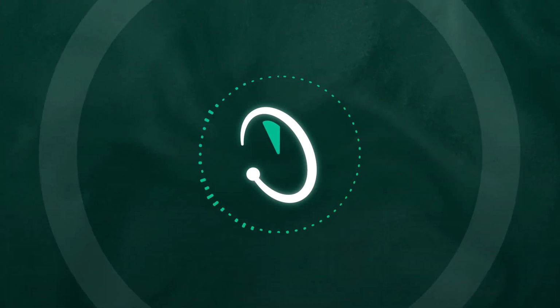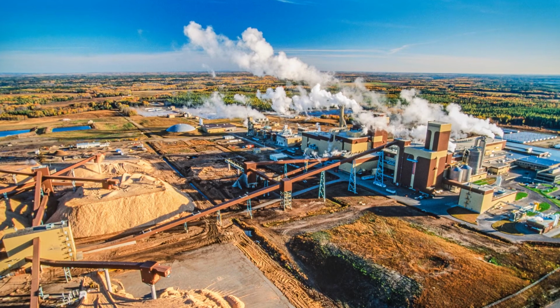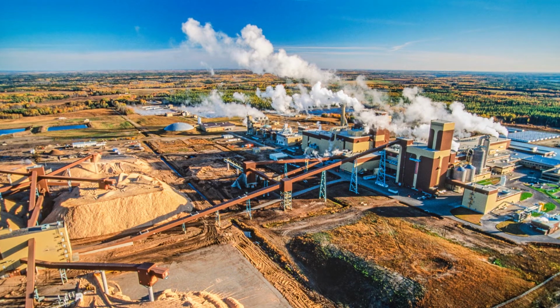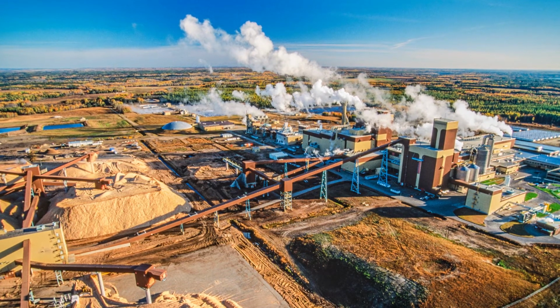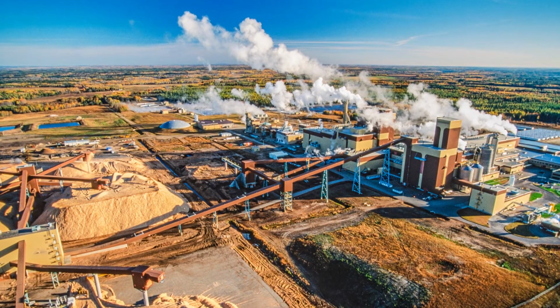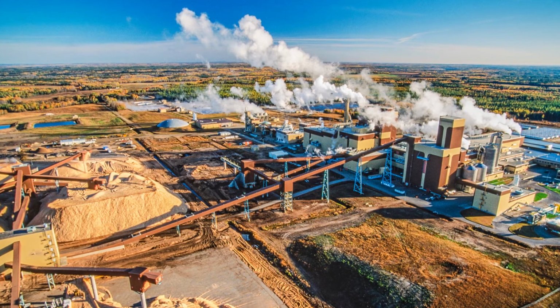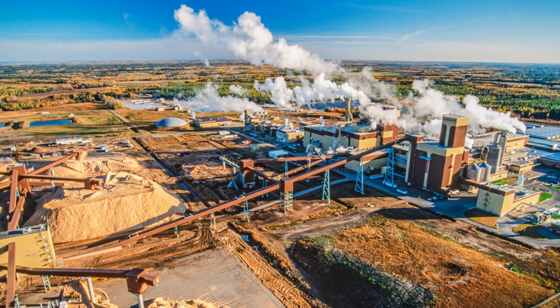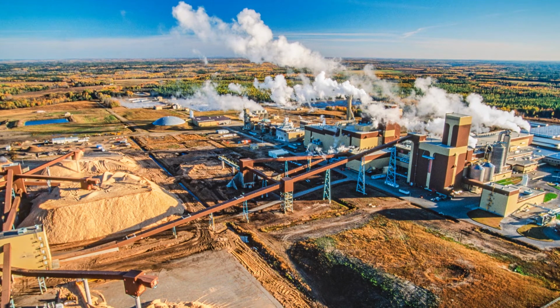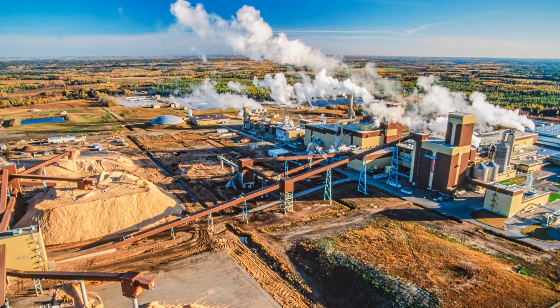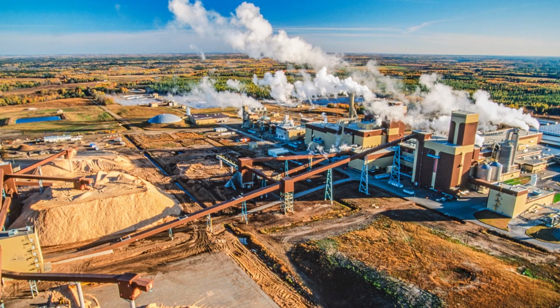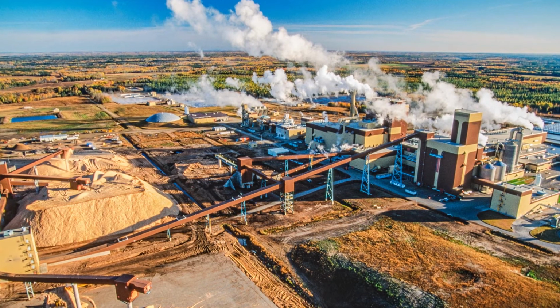So what I mean by that is we call this data on severity. The sensor itself has two levels, kind of an alert and alarm type level settings, where you would set the vibration characteristic that you want it not to exceed, and the sensor itself will wake up, of course, and take its reading. If it detects that it's above the alert level, it will take some predefined actions.